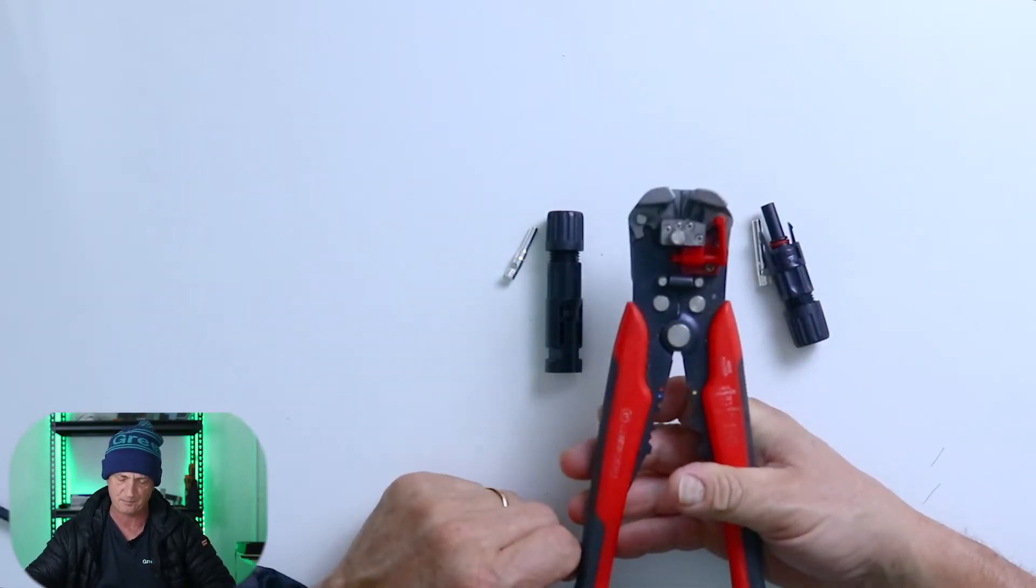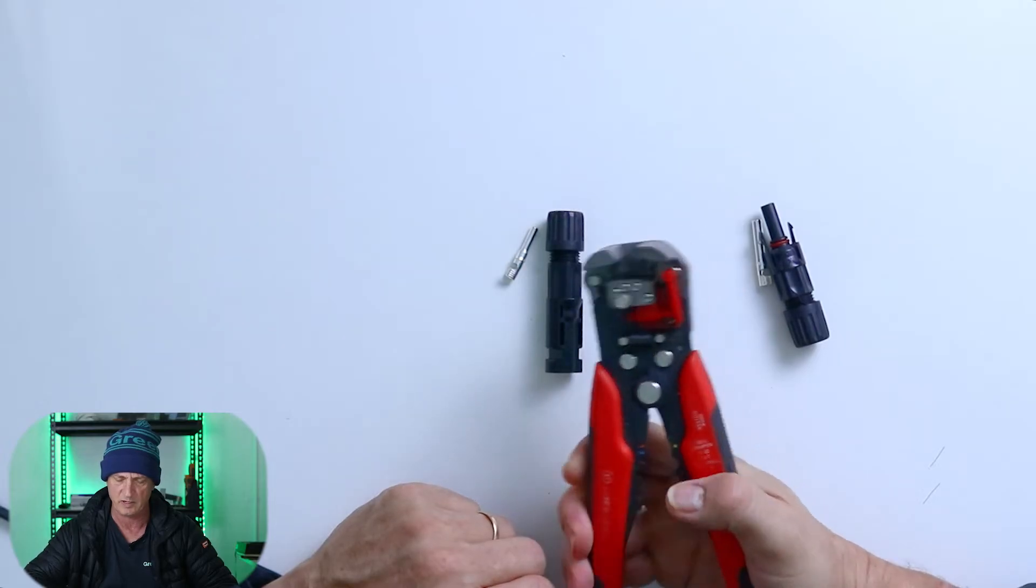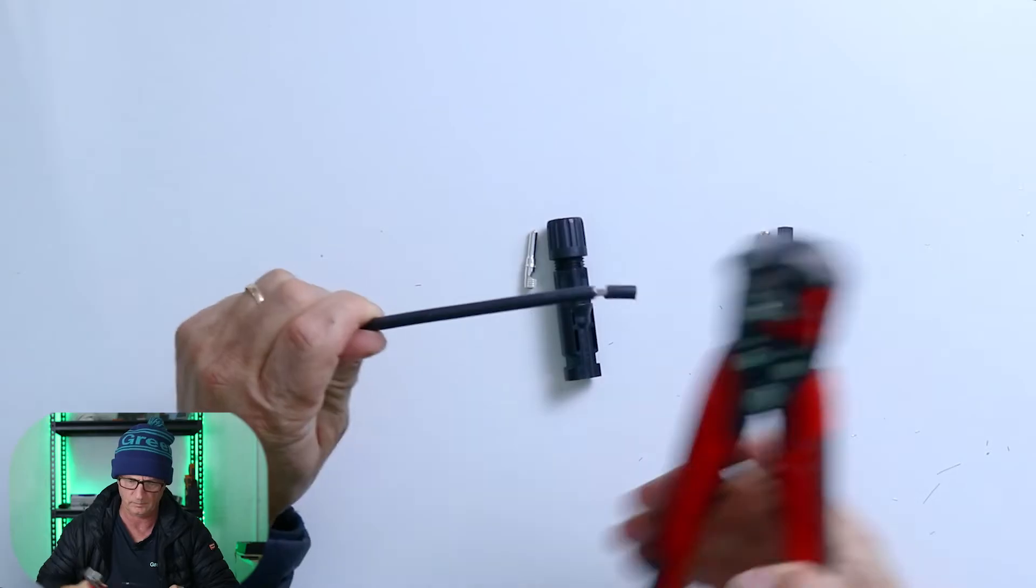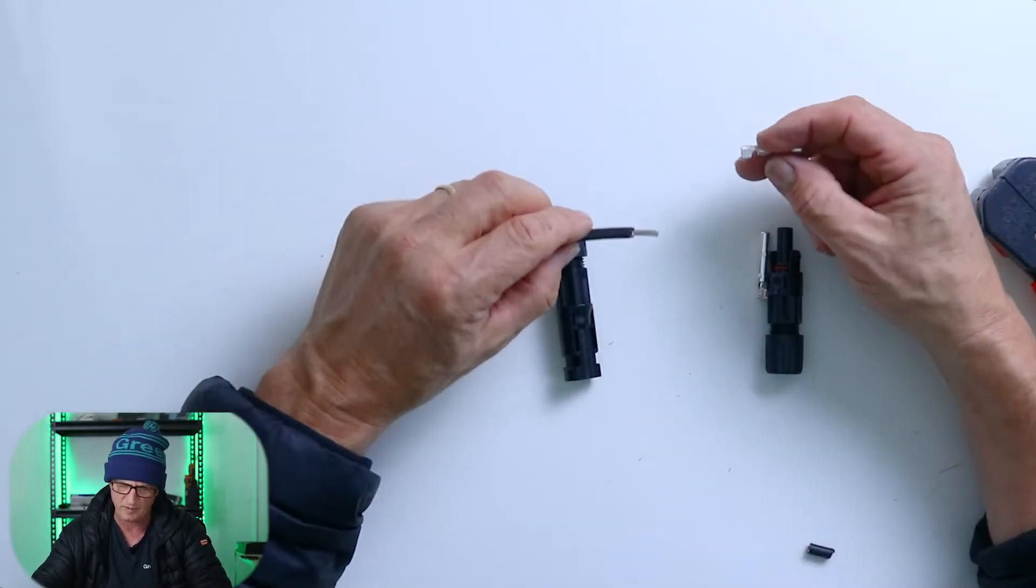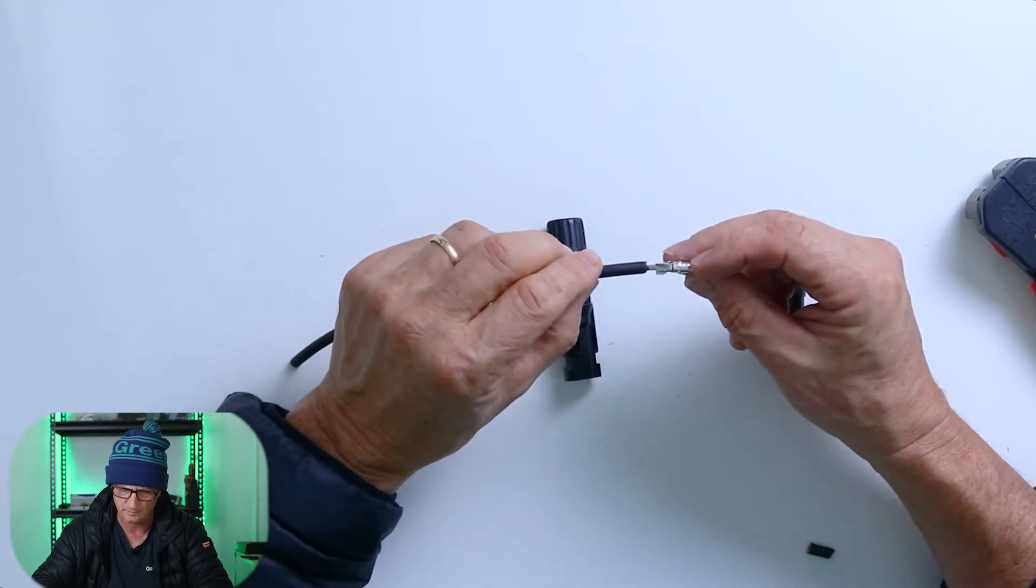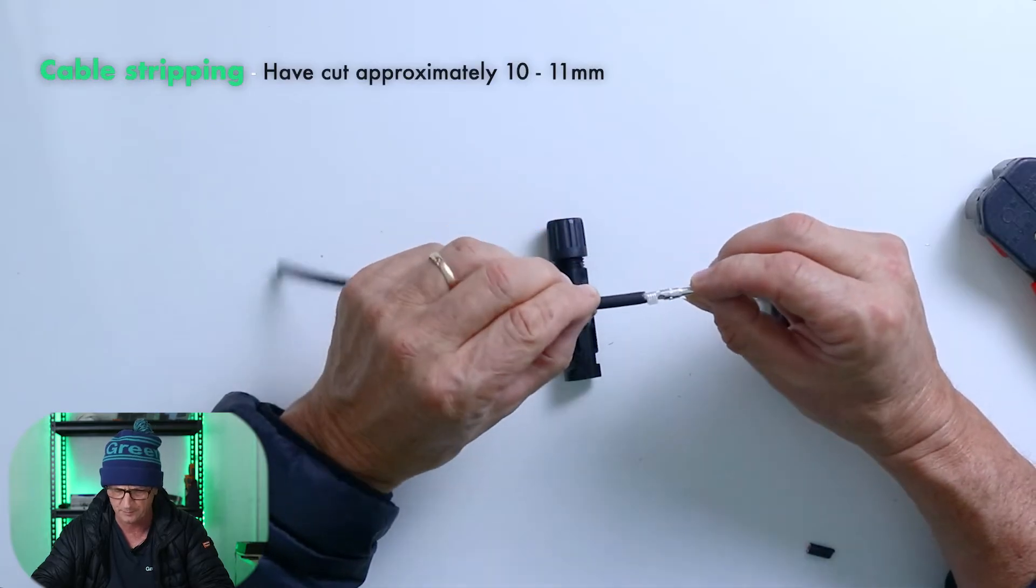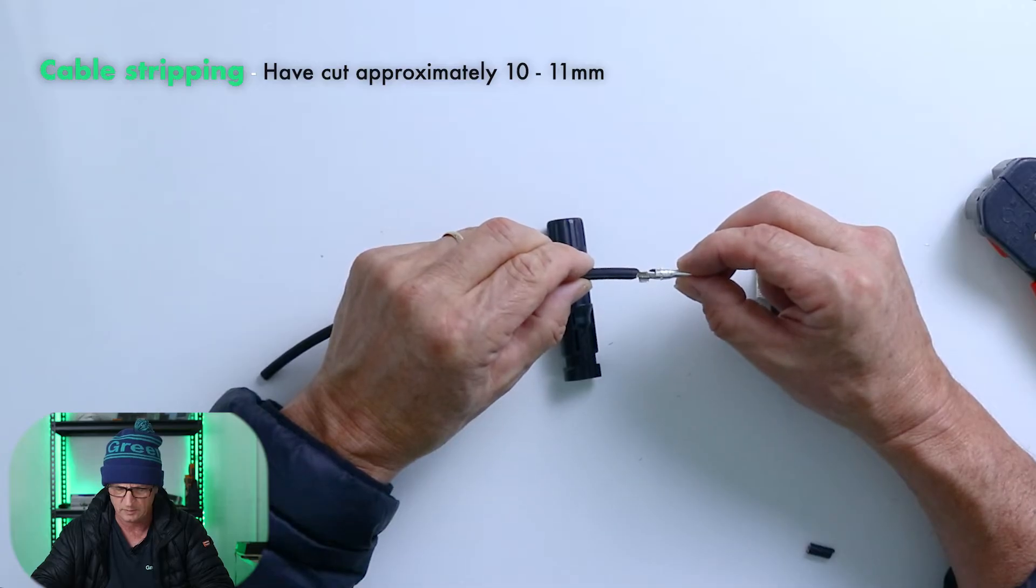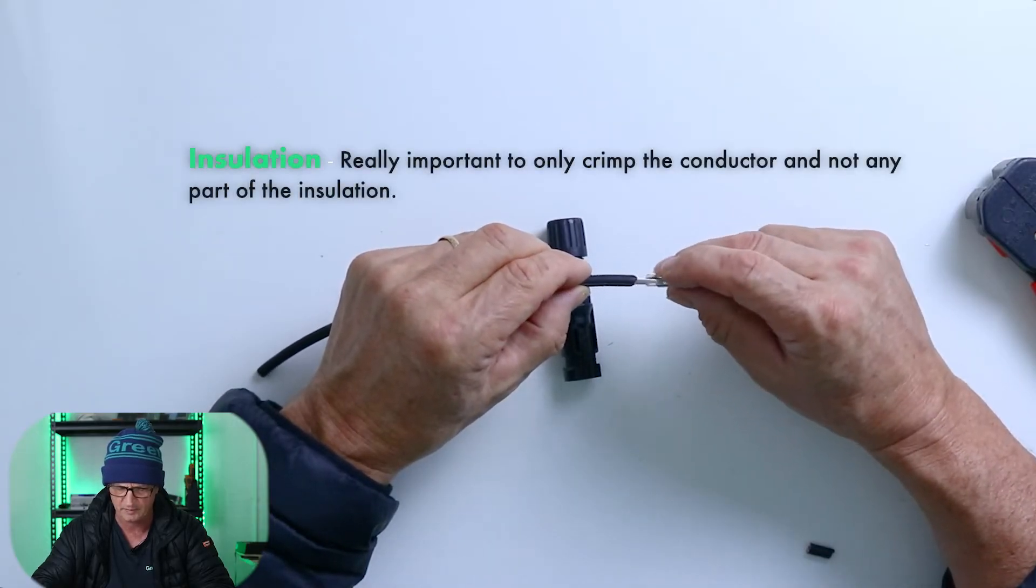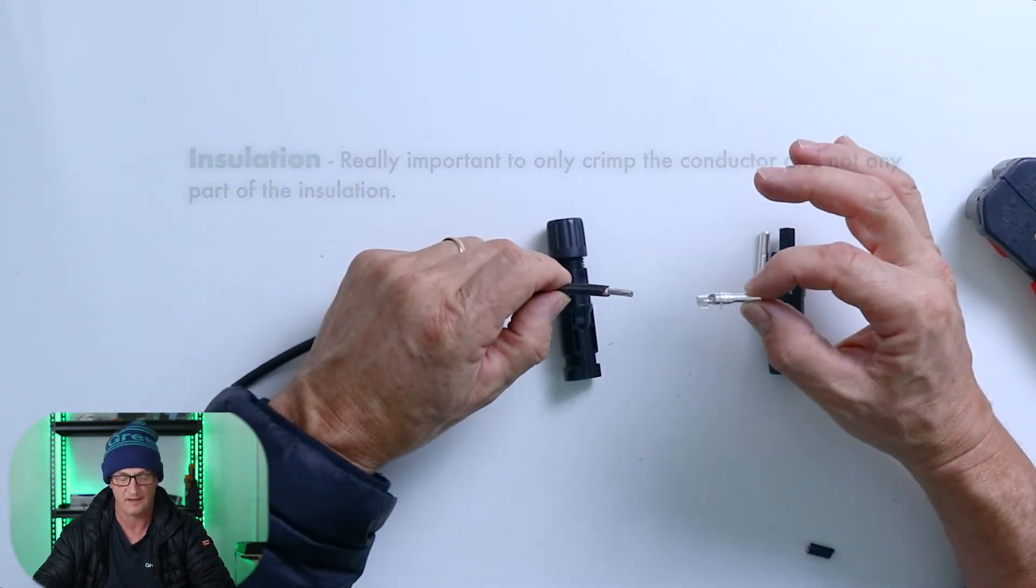So with these particular cable strippers, you can see the action cable goes in here, presses down, separates. Now you can see I've cut probably 10, 11 mil. And I place it in here. Making sure that there are no strands. Now notice how I have left maybe half a mil between the insulation and the actual tabs. You don't want to make this too long at all. Because if you do, you'll have to cut it. So I've got the male insert, which goes into the female MC4.